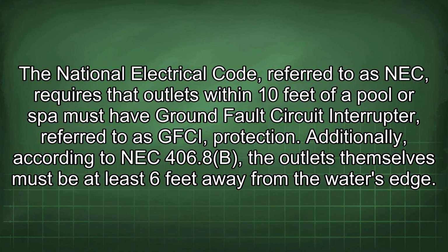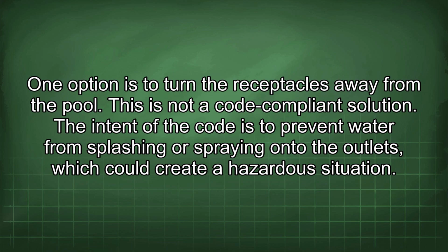The National Electrical Code, referred to as NEC, requires that outlets within 10 feet of a pool or spa must have ground fault circuit interrupter, referred to as GFCI, protection. Additionally, according to NEC 406.8b, the outlets themselves must be at least 6 feet away from the water's edge. One option is to turn the receptacles away from the pool. This is not a code-compliant solution.